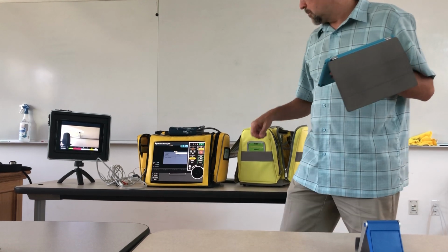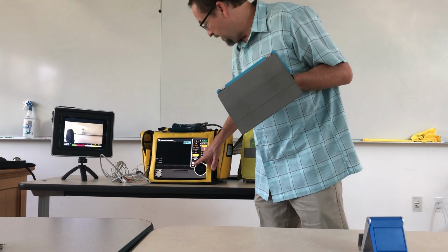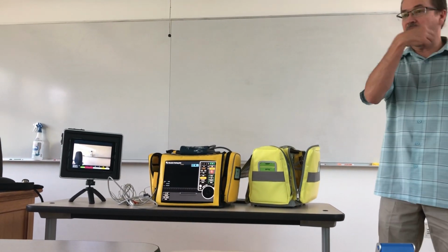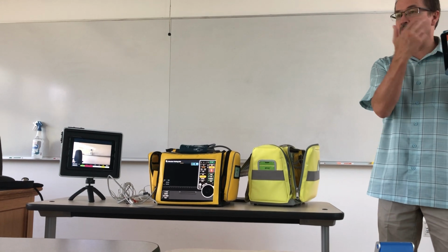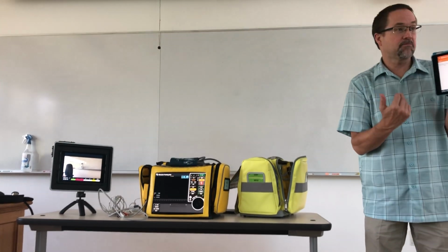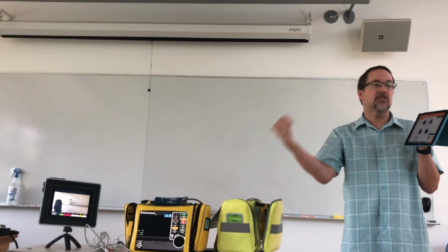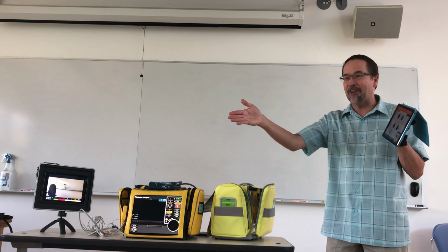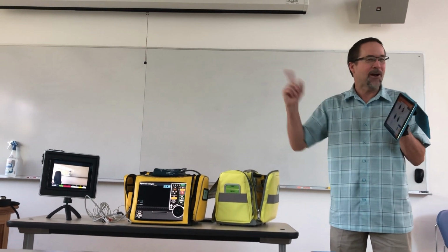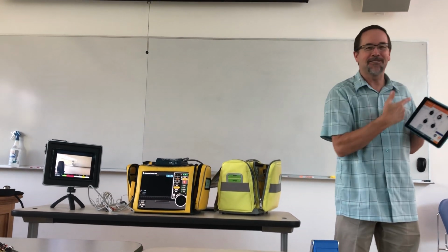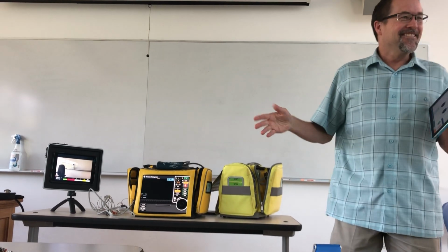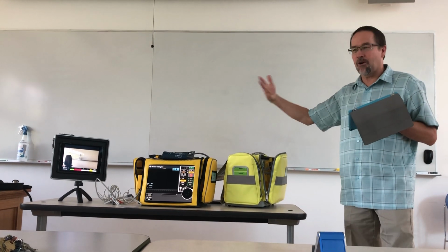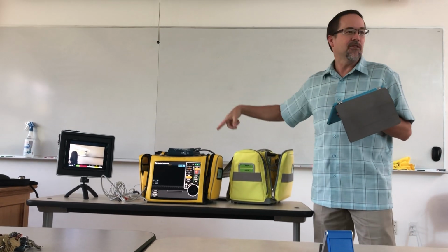And you can do full pacing, synchronize, the whole nine yards. Yeah, absolutely. And with the pacing, you can go in your scenario settings and tell it where you want the pacing to be successful, or you don't want the pacing to be successful. So you can set what energy level it's going to take for the capture. Unlike our old rhythm generators, where every student, once they've gone through it once, knows 70 is how high you go, and they get pre-programmed to think, oh, you just hit that thing till it's 70 and then move on to the next thing because it's going to capture, right? You can set it lower, exactly. You can set it where you want, and it will respond the way it ought to.